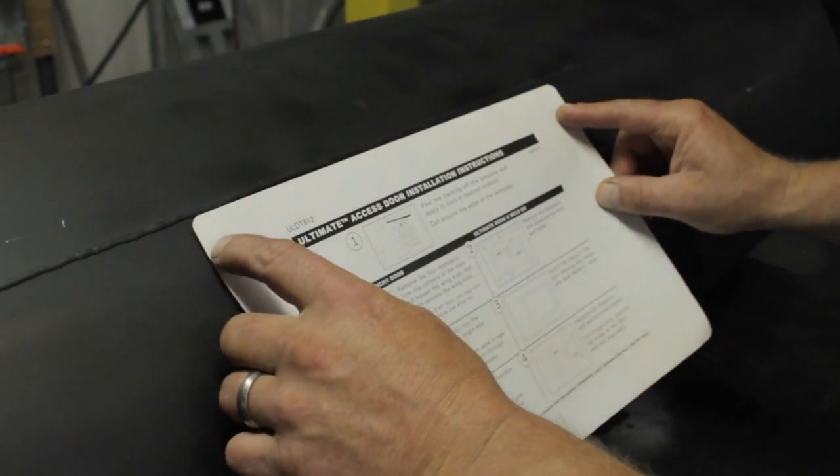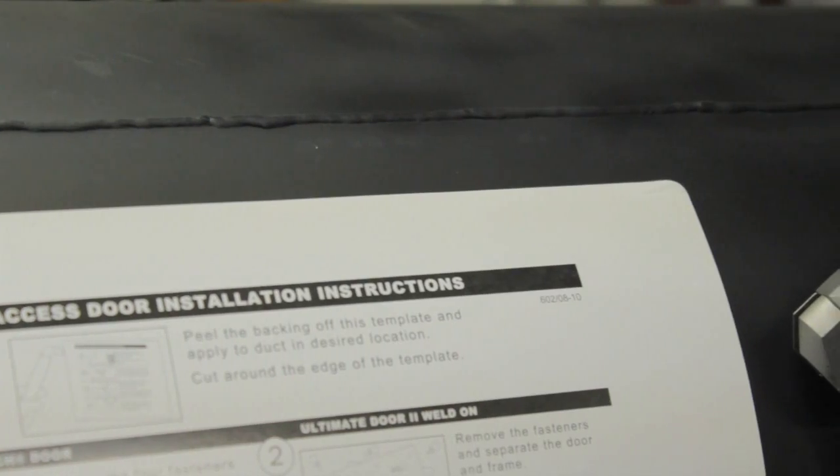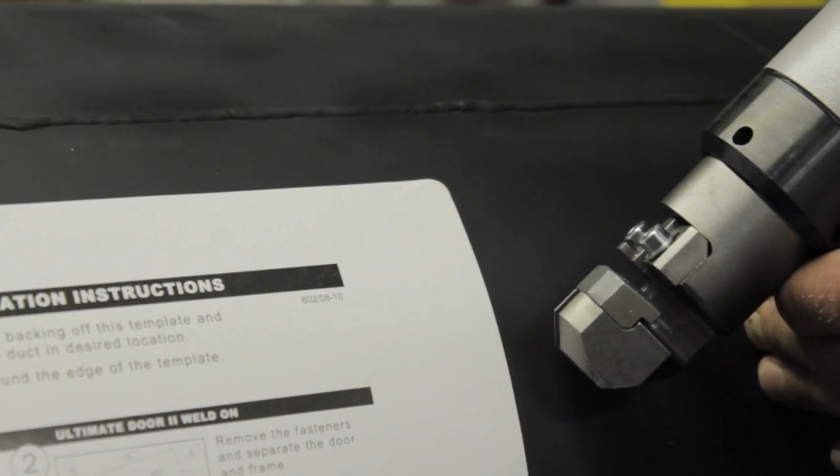The door frame extends one inch around the opening. Therefore, a minimum of one inch clearance is required on either side of the welded seam. Cutting the opening too close to the welded seam may lead to leakage.